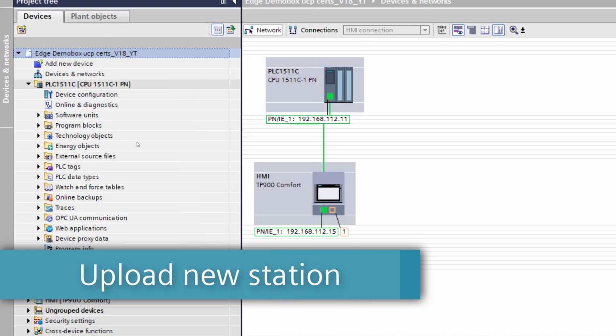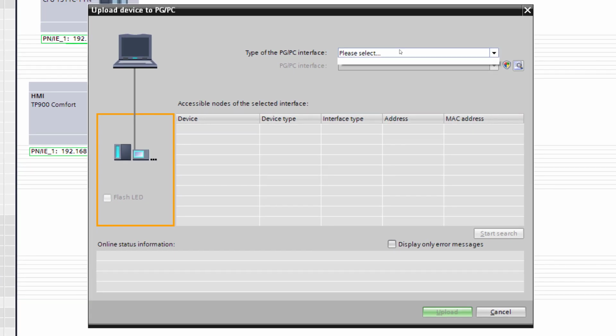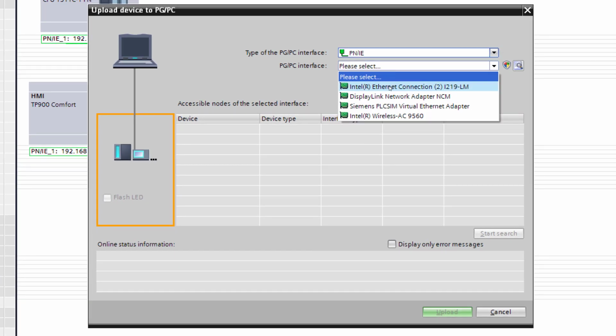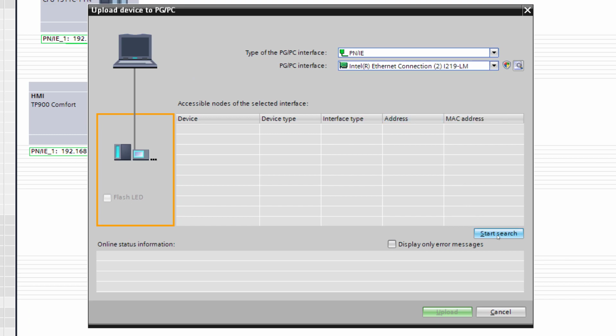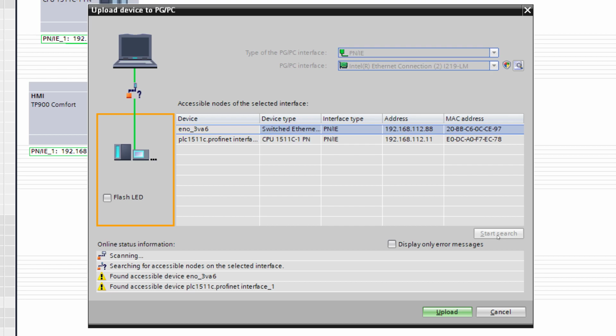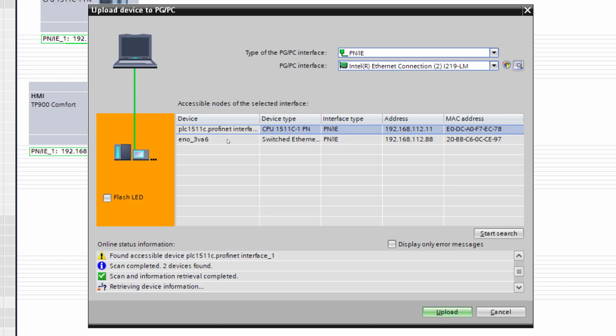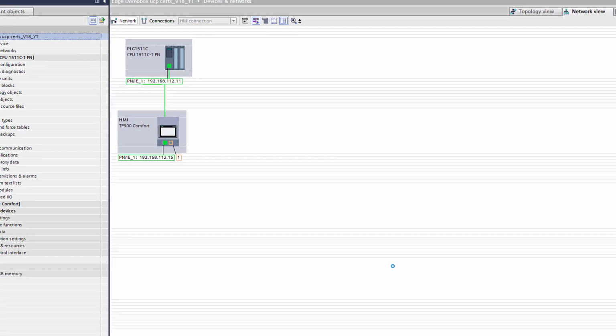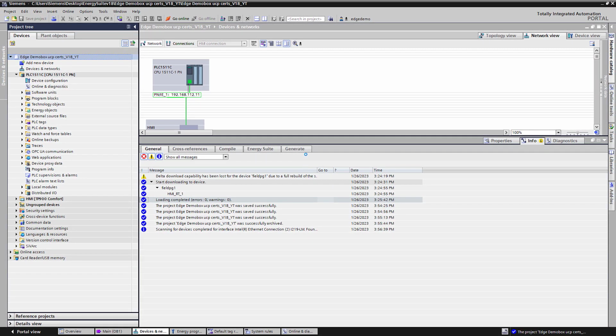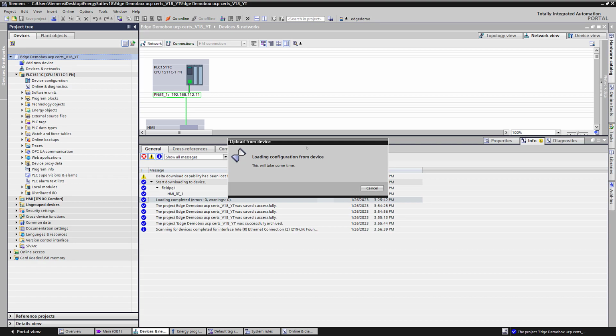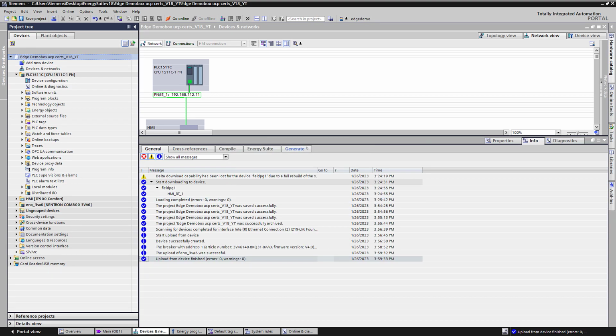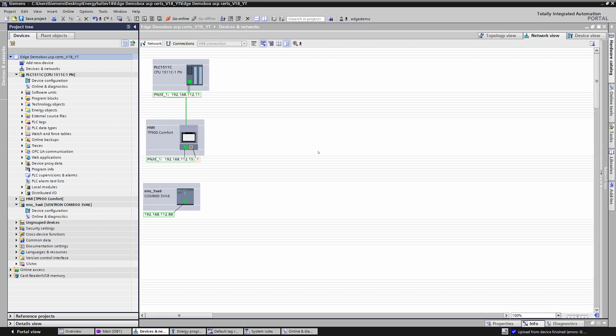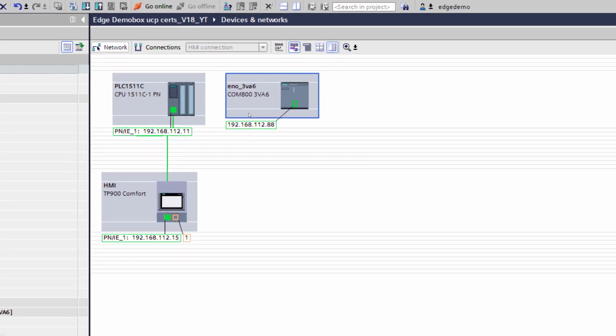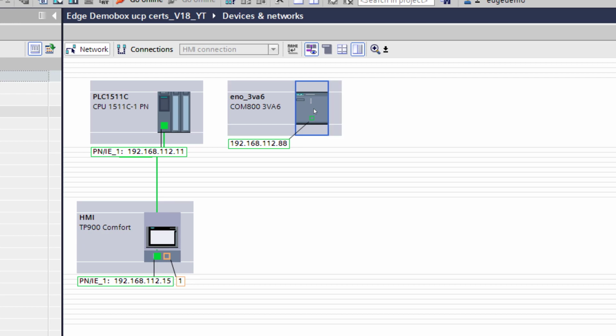So what's next is that we can use Profinet to our advantage and discover the device and upload it as a new station. This allows us to bypass having to build it piece by piece. We'll go ahead and select the ENO3VA6, the switched Ethernet expansion module, and hit upload. So now with the module in place, it's visible within the network view, but also the project tree. Double-clicking or using the tab device view brings us into the device viewer. This is where bulk of the programming and configuration of the device is determined.